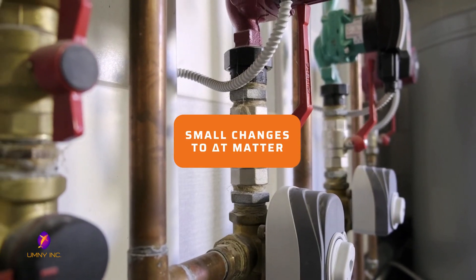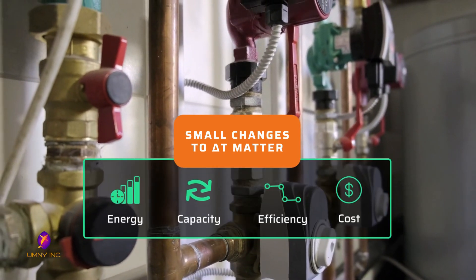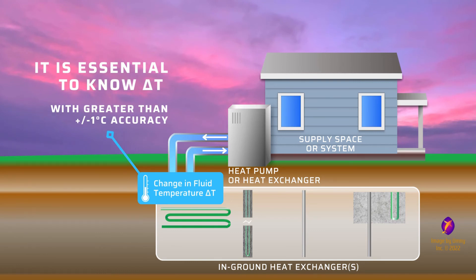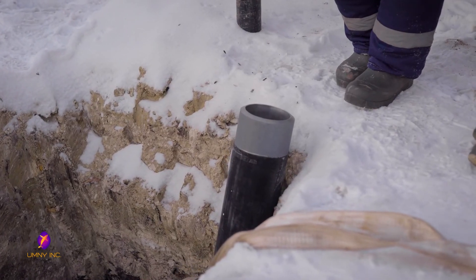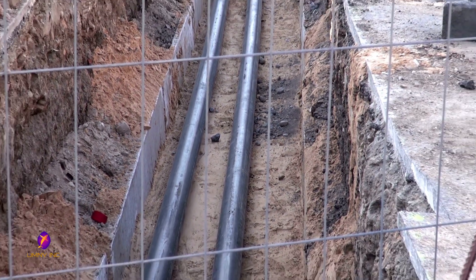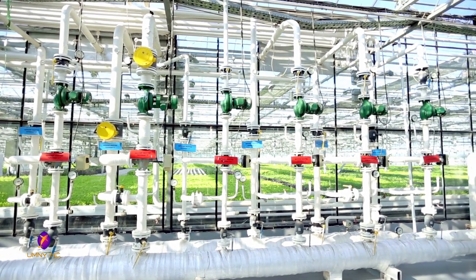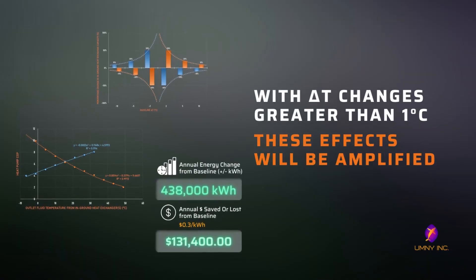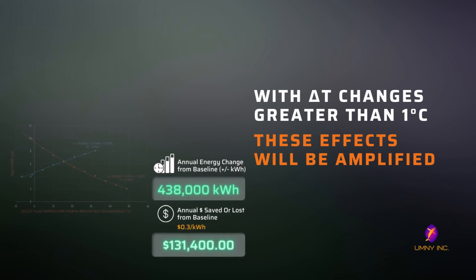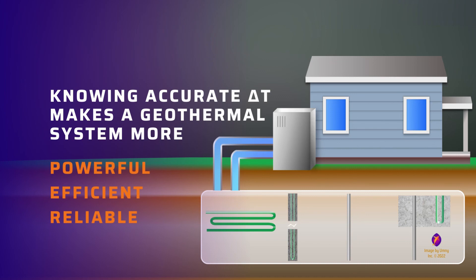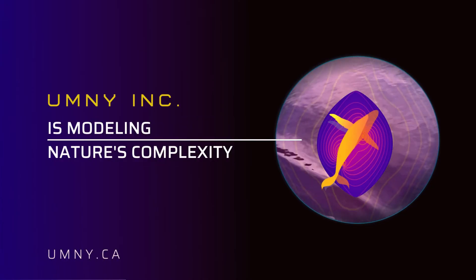Even though it may seem that 1 degree Celsius is a small change that can be ignored in geothermal systems, this change can have a significant impact on performance, efficiency, and cost. It is essential that in the design and operating stages, temperature change across the in-ground heat exchangers is calculated or measured with a tighter accuracy than plus or minus 1 degree. Choices in underground piping — such as foregoing insulation on supply and return lines, spacing close enough to experience thermal interference from other equipment, or having auxiliary systems connected to the same loop — can result in fluid temperature changes beyond the baseline delta T of at least plus or minus 1 degree Celsius. If temperature changes exceed just 1 degree, all effects on performance, efficiency, and cost would be amplified even more. By paying close attention to the change in fluid temperatures, a geothermal system can be more powerful, efficient, and reliable. Head over to the UMNY blog for more information about these calculations and effects.